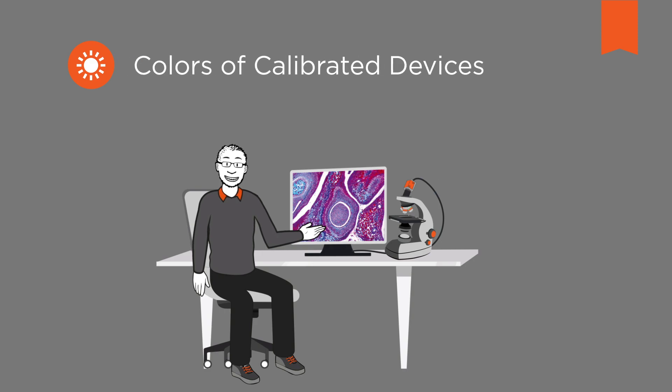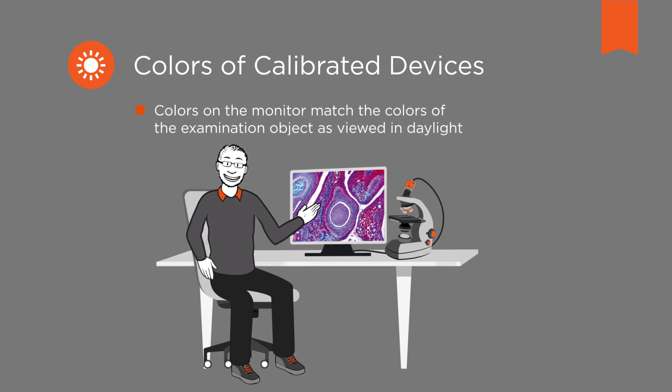Standardization leads to high accuracy, including high color fidelity. The process in which color reproduction is standardized is called color calibration. When image acquisition devices are calibrated, the colors of the acquired images seen on the monitor match the colors of the examination object as viewed in daylight.